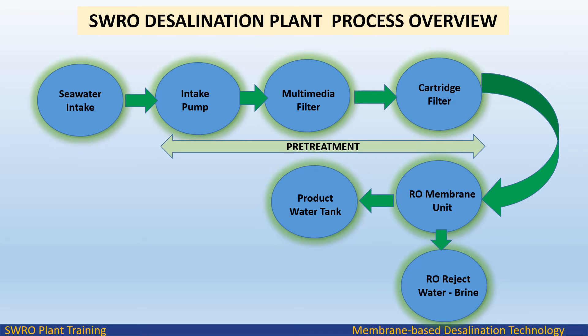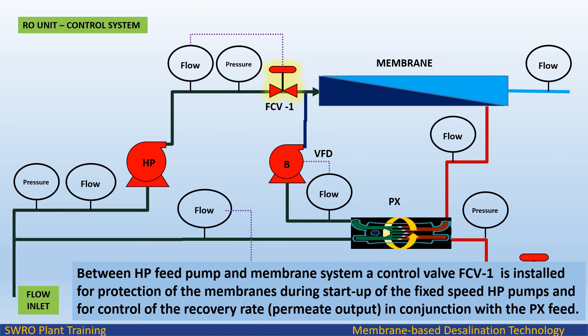In the SWRO desalination plant process diagram overview, feed water from the cartridge filter passes to the RO membrane unit. Between the HP feed pump and the membrane system, a control valve FCV1 is installed for protection of the membranes during start-up of the fixed-speed HP pumps and for control of the recovery rate and permeate output in conjunction with the PX feed.